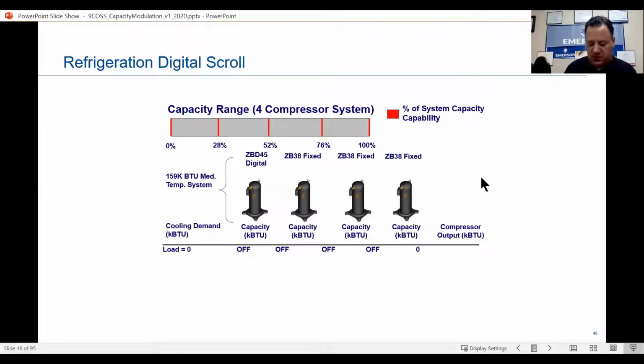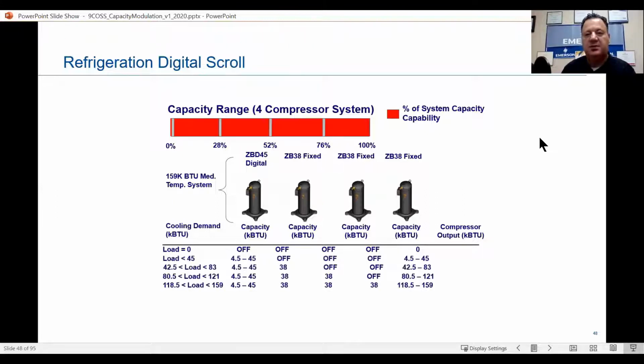So that's how digital works in a rack system. It load matches that, okay? It matches the load, the next fixed compressor that comes on. So if you get in an opportunity where a compressor goes down on a rack, this would be a great opportunity to help a customer out to add that digital compressor.